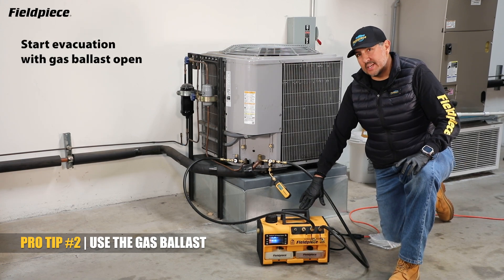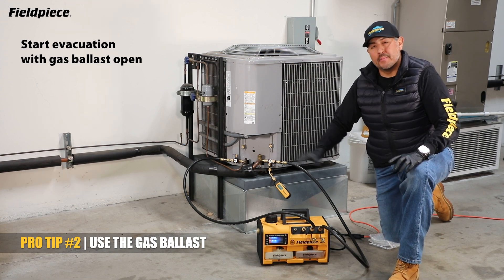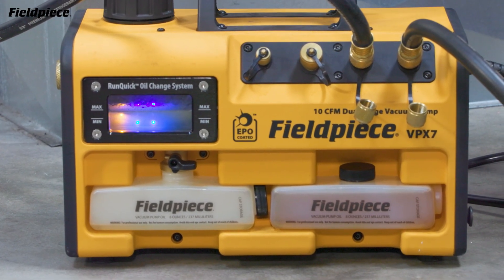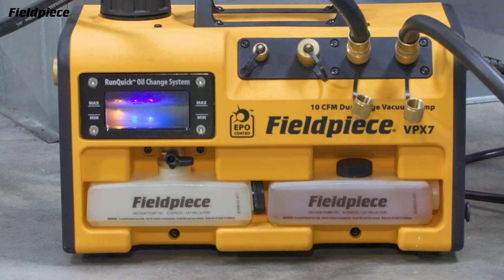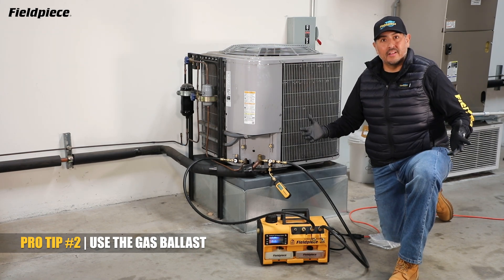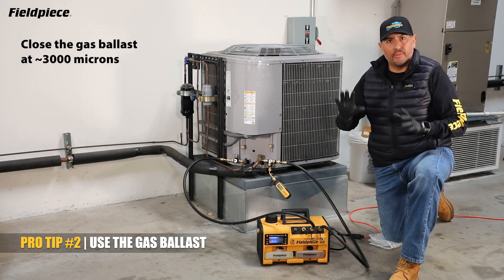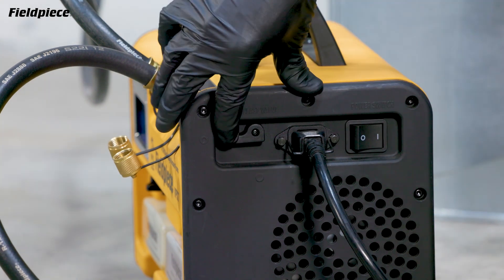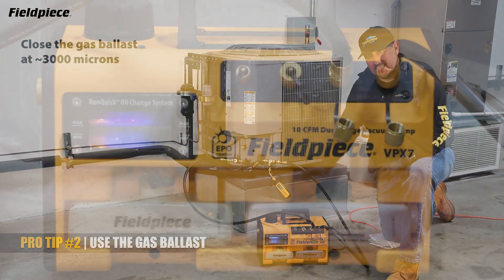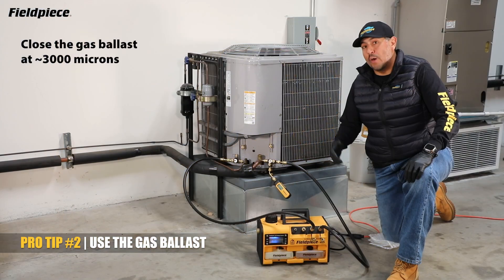With the ballast open, the pump is going to run a little bit louder and there might be more exhaust coming out the side of your pump. That's because with the ballast open, it's allowing some outside air through the pump in order to exhaust more of the water vapor coming from the initial stages of evacuation, rather than letting it deposit into the vacuum pump oil, thus extending the life of the oil. When most of the moisture is gone from your system or when you're around 3000 microns, go ahead and close your gas ballast so that your vacuum pump can achieve a really deep vacuum. On the Fieldpiece pumps, you have a blinking yellow LED to indicate that your gas ballast is open so you don't forget to close it.